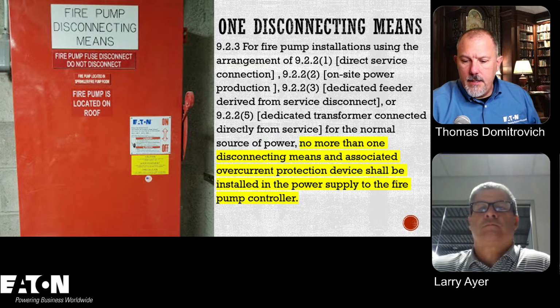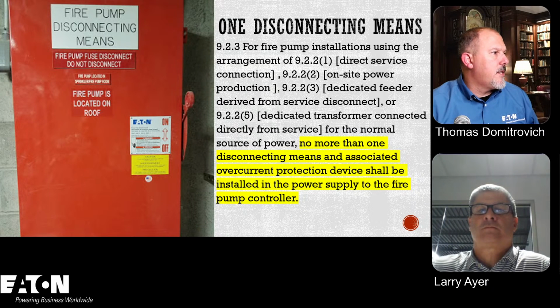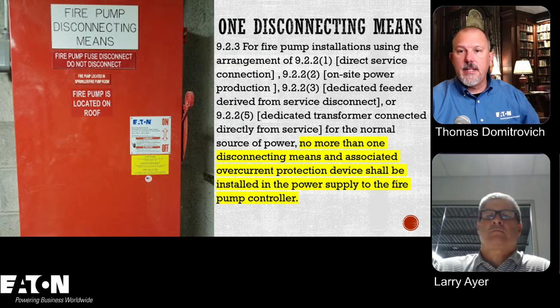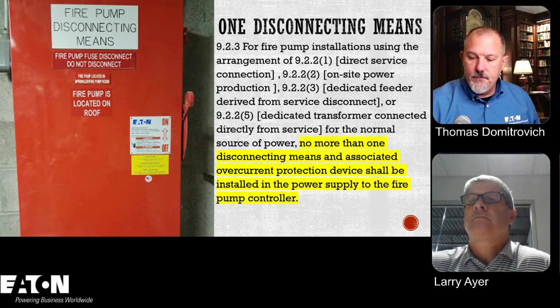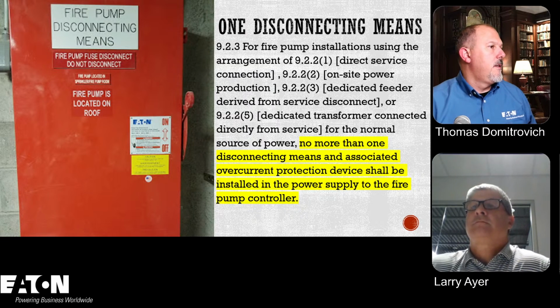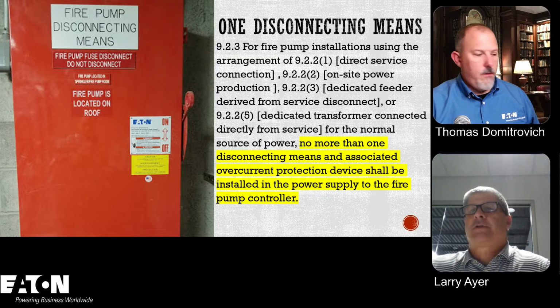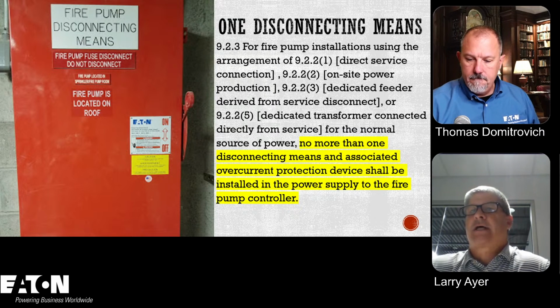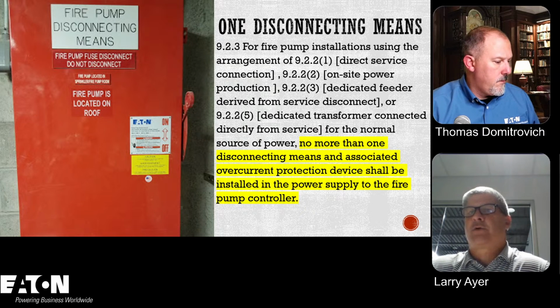All right. So disconnecting means, you're going to need a disconnect. Right. So this is the whole key. You just want one disconnect in the system between the service and the fire pump controller. So this is 9.2.3.